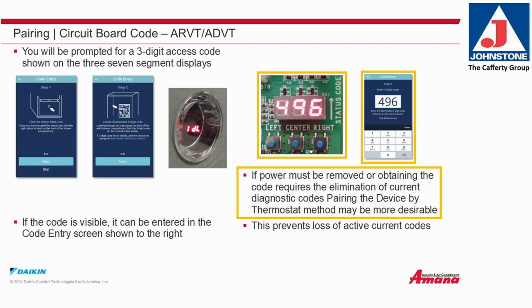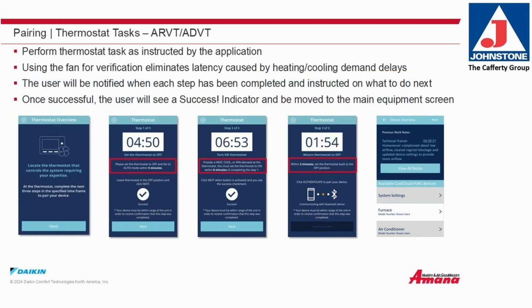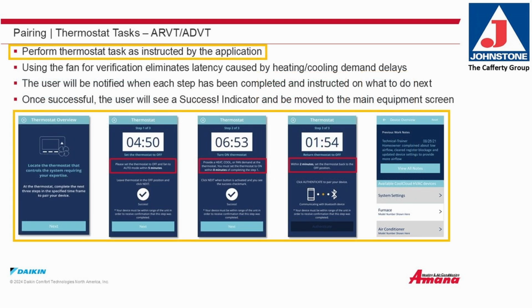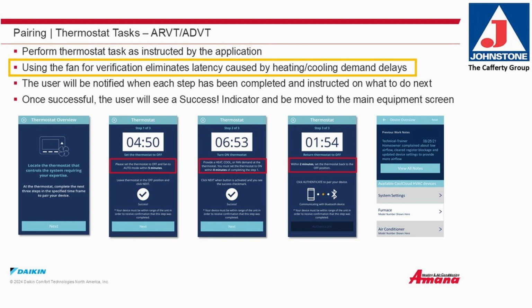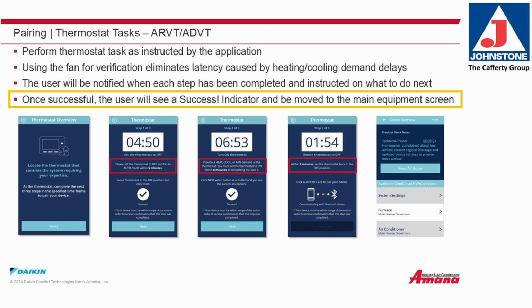If power must be removed, or if getting the code requires you to eliminate the current diagnostic codes, then pairing the device by thermostat method may be more desirable. This prevents the loss of an active diagnostic code. Pairing thermostat tasks. Perform the thermostat task as instructed by the application. Using the fan for verification eliminates latency caused by the heating-cooling demand delays. The user will be notified when each step has been completed and instructed on what to do next. Once successful, the user will see a success indicator and be moved to the main equipment screen.